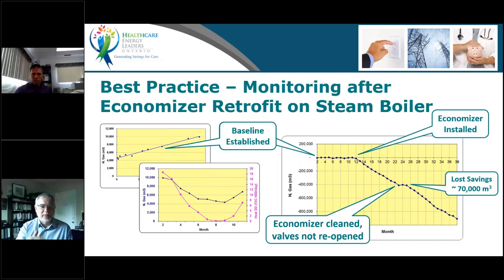That was used as a baseline to then generate one of these things called a CUSUM. We'll talk more about this later in modules 12 and 13 on tools. A CUSUM allows you to look at the cumulative sum of the difference between what you expected to consume using your baseline and what you actually consumed. It was interesting because when they generated the CUSUM line, the person from the hospital couldn't explain why that line started to descend at month 12. Eventually he went back and said, "Yeah, okay, that was when we installed the economizer." So this is evidence of savings from the economizer. Pretty dramatic savings, actually. But then it took him about 3 weeks to figure out what happened when that CUSUM line went horizontal around month 23.